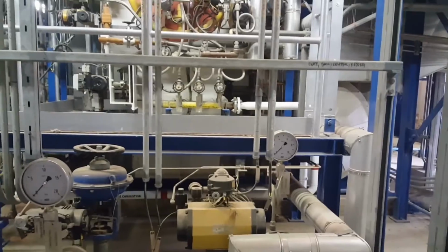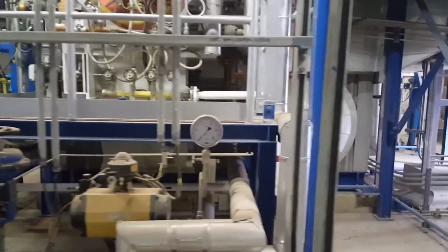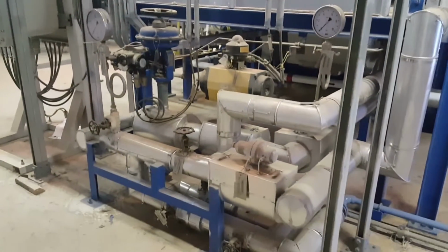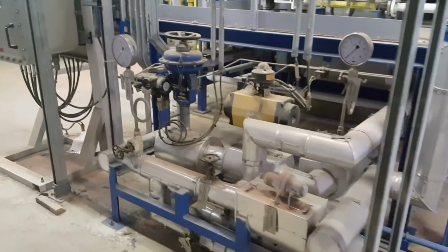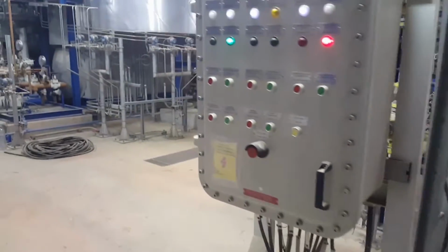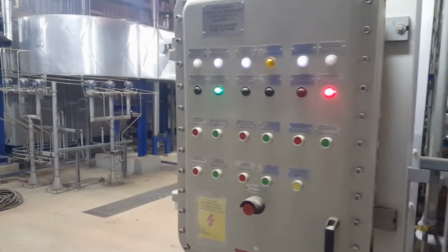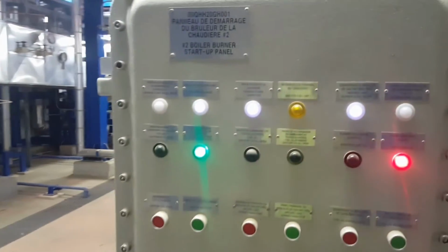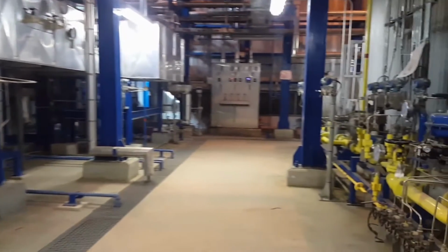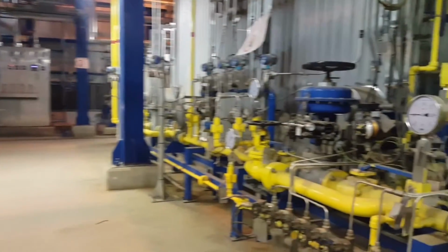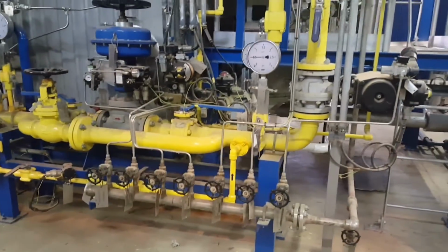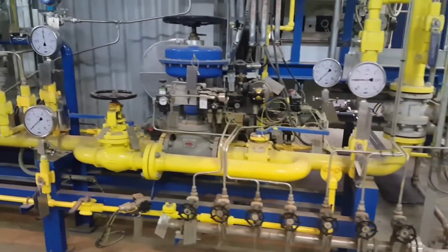Since oil is a liquid, it has to be changed into a mist or atomized before it can mix well with air and burn. This example is a mechanical atomizer. Mechanical atomizers depend on the pressure of oil passing through a nozzle to produce a fine mist. Fuel entering the atomizer flows to a sprayer head. The oil is forced through the nozzle, which breaks the oil into droplets. The droplets are sprayed into the combustion area in the form of a fine mist.